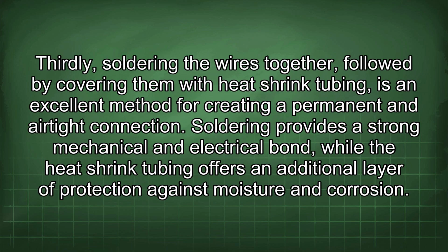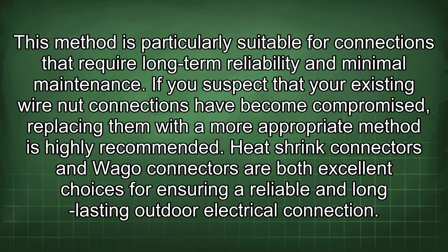Thirdly, soldering the wires together, followed by covering them with heat shrink tubing, is an excellent method for creating a permanent and airtight connection. Soldering provides a strong mechanical and electrical bond, while the heat shrink tubing offers an additional layer of protection against moisture and corrosion. This method is particularly suitable for connections that require long-term reliability and minimal maintenance.